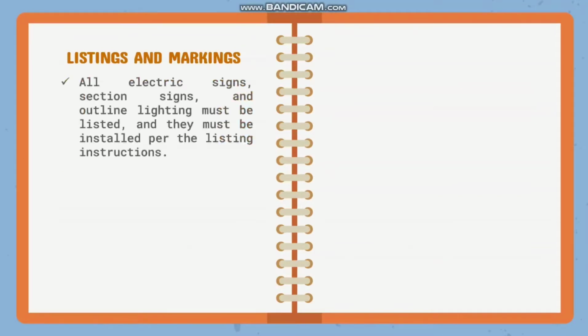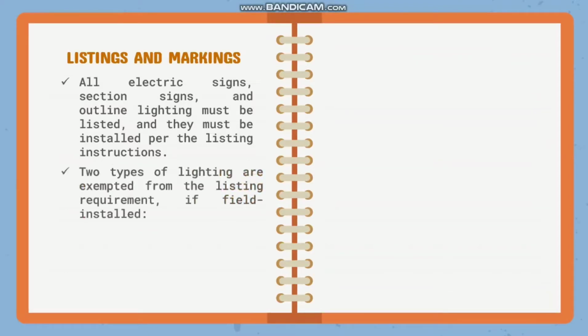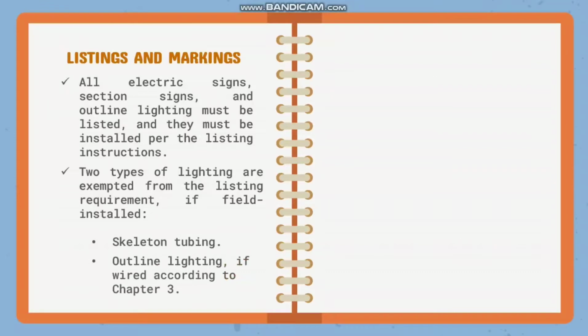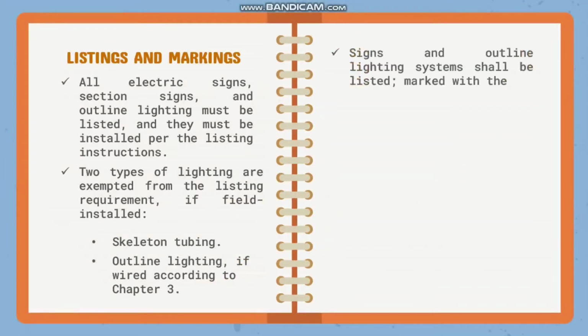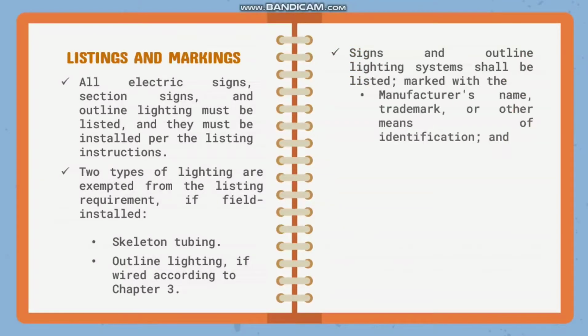So for the listings and markings, all electric signs, section signs, and outline lighting must be listed and they must be installed per the listing instructions. Two types of lighting are exempted from the listing requirement if field installed. So the skeleton tubing and the outline lighting if wired according to Chapter 3. Signs and outline lighting system shall be listed and marked with the manufacturer's name, trademark, or other means of identification, and input voltage and current rating.